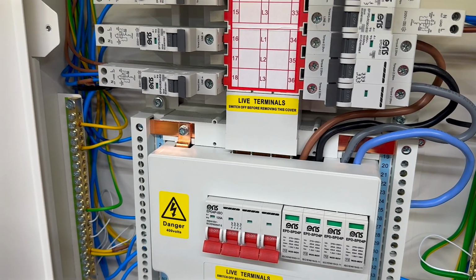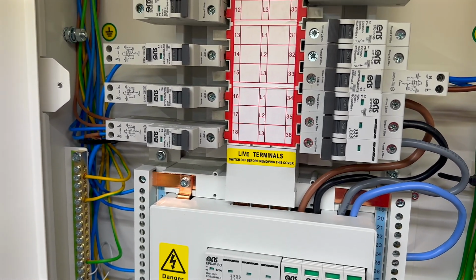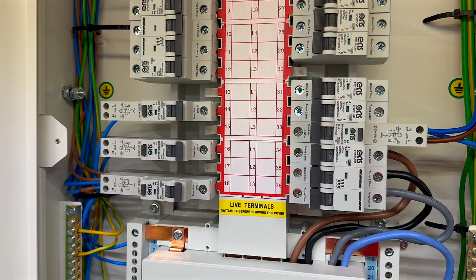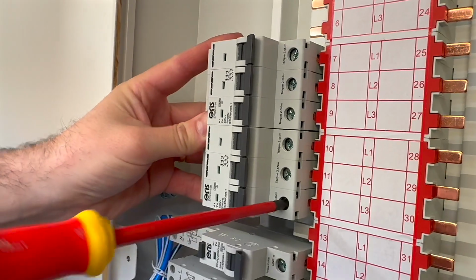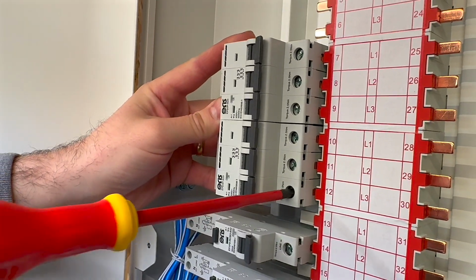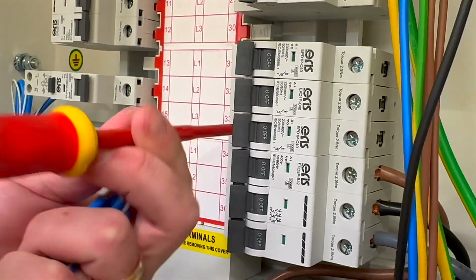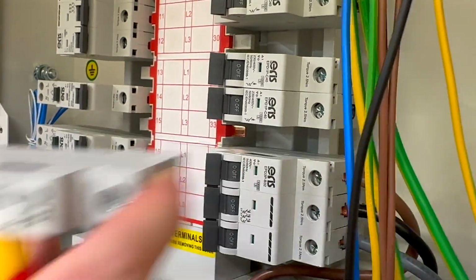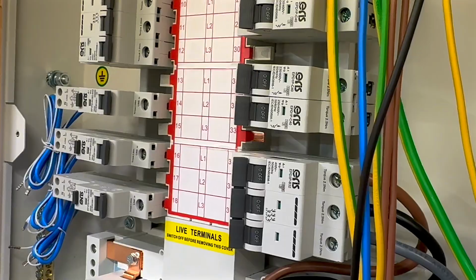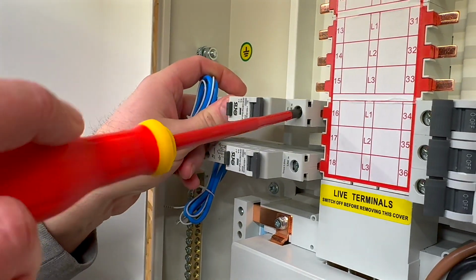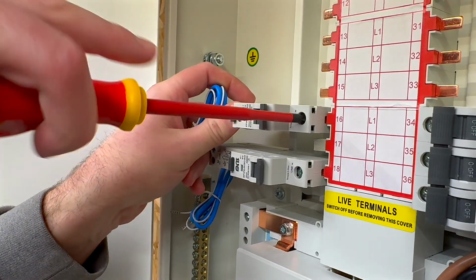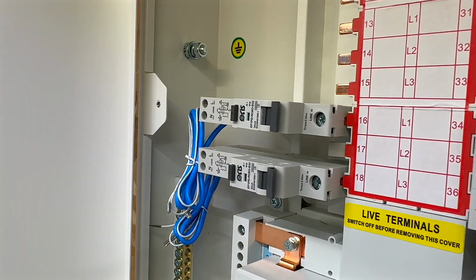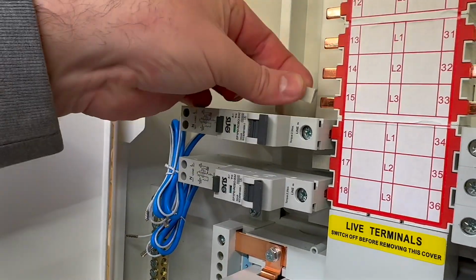3-phase boards offer a flexible solution for organising outgoing circuits. In mixed boards containing both single-phase and 3-phase circuits, it can be beneficial to group 3-phase circuits on one side and single-phase circuits on the other. Special attention should be given to circuits that experience continuous rated loads over extended periods, as the heat generated can impact the performance of nearby devices.